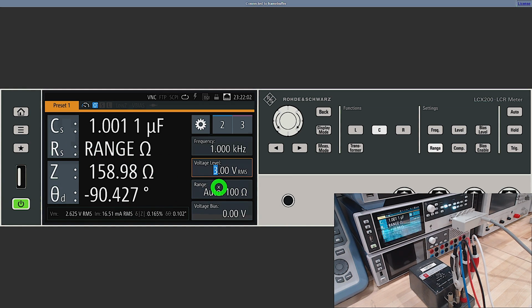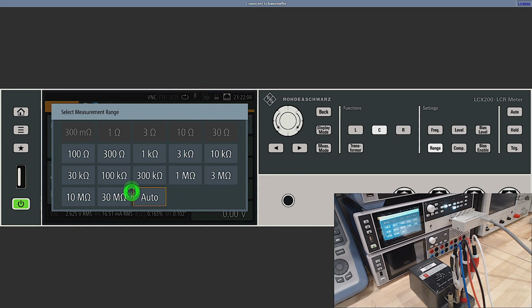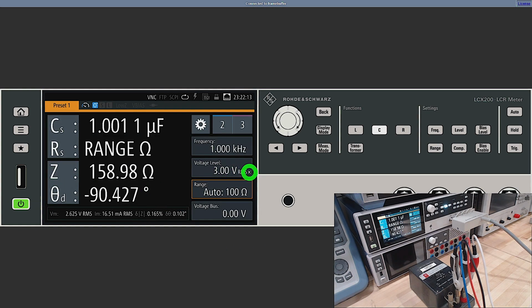In fact, 100 ohm is the smallest range I have in this case anyway, so even if I remove the auto ranging, I still won't be able to measure it. These ranges are not available in this condition. I'll show you why in just a second. So it means that with 3 volts RMS, I can still get my impedance measurements, and the measurements of the voltage and the current are there, but unfortunately I can no longer get the RS measurement as a result of that.